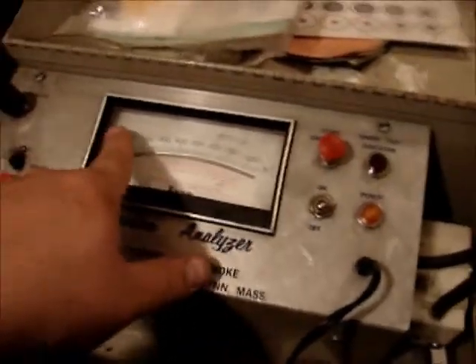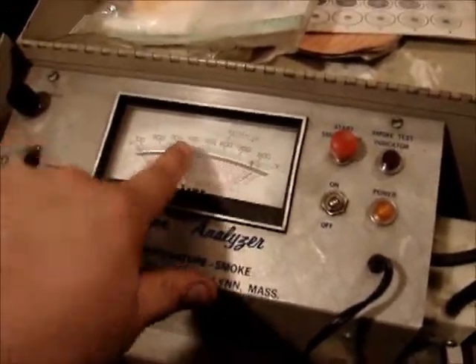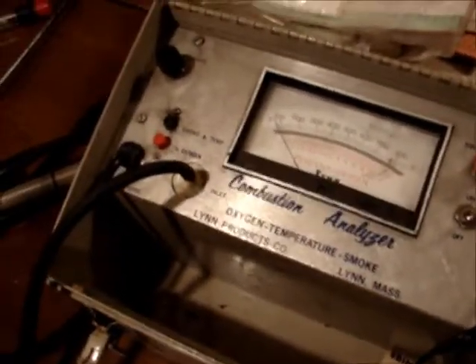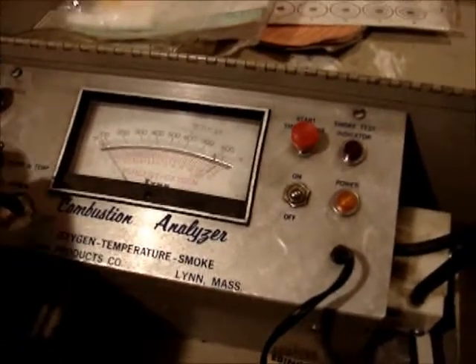The temperature works. I put it in the burner on the gas stove, and the needle came right up to like 500 degrees. And the vacuum pump works, it does draw the gas through the unit, but you get no deflection when you put it on the oxygen scale. I pulled the oxygen sensor out of here, and it's all corroded, and it's probably no good. So I don't know if you can get one. I tried doing a little search online.